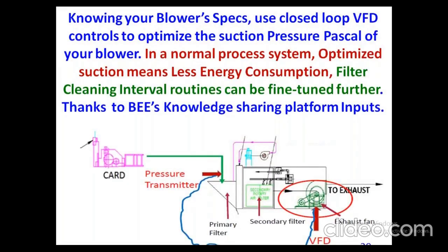One is the impeller, the next one is closed loop control. A typical waste collection system, not only in the textile mill, is applicable in the engineering industry and in the foundry also. A carding machine needs only 600 Pascal suction, which means you maintain 600 Pascal. Instead of that, you are maintaining 2200 Pascal at the motor. From 2200 Pascal you bring it down to 1600 at the primary filter, then to 1200 on the secondary filter, then from 1200 to 900, then they give it to 600. This much loss gradient need not happen.